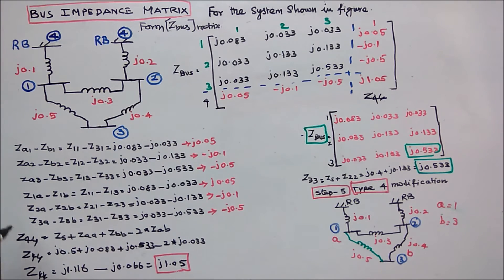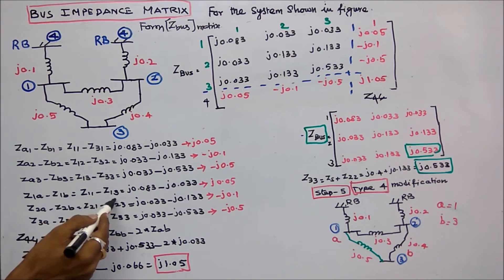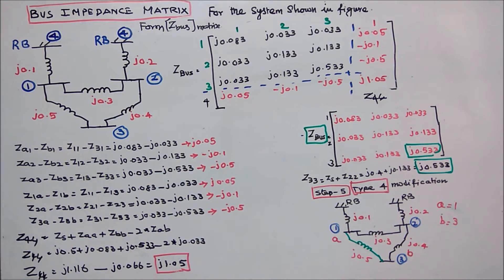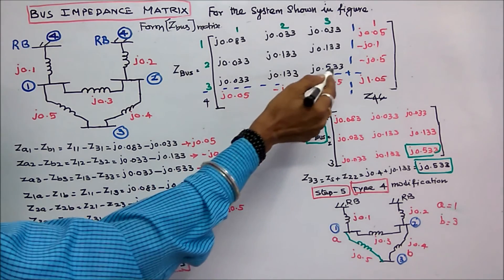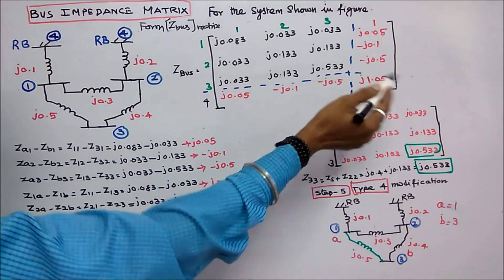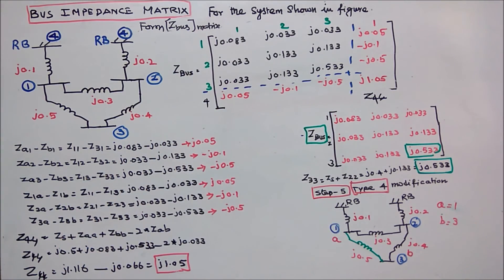Z14 equals Z1a minus Z1b equals Z11 minus Z13 equals j0.05. The next value Z24 is minus j0.1, and Z34 is minus j0.5. Z44 formula is: Zs plus Zaa plus Zbb minus 2 times Zab, where Zs equals j0.5, Z11 equals j0.083, Z33 equals j0.533, and Z13 equals j0.033. Z44 equals j1.05. Now we have a four by four matrix and we have to reduce it to a three by three matrix using Kron's method.